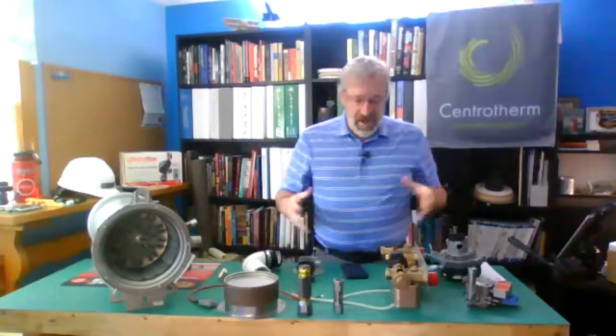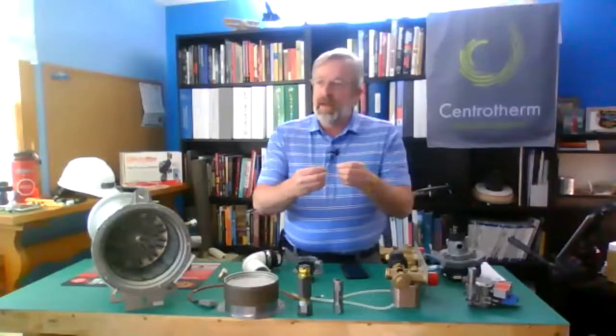But let's talk a little bit about all this stuff that I've got right here, what we just talked about. So we're going to go through, and I always hate to start with a problem, but it walks me right into cleaning the heat exchanger over here. So combustion system, call for heat. Turn my fan on, run my fan up to where I want to be as far as my firing rate. When I get to that point in time, what I do is I open up my gas valve, spark, light. If that doesn't happen, let's walk back through where we needed to be.